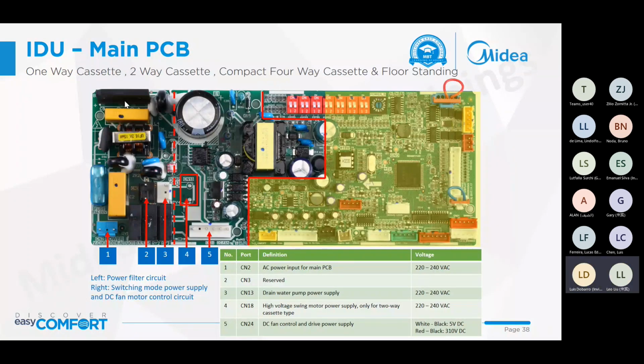Okay, for the indoor unit, usually we have two types of indoor PCB. This type of PCB is for one-way cassette, two-way cassette, compact four-way cassette, and the floor standing. These four types of indoor unit use the same shape of indoor PCB. The right area has the DIP switch, ports, and the chips.